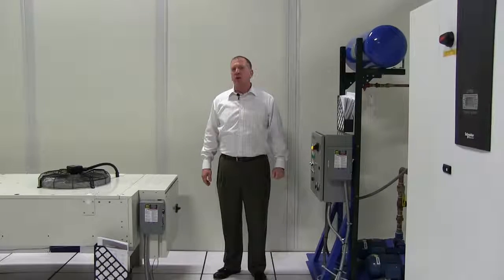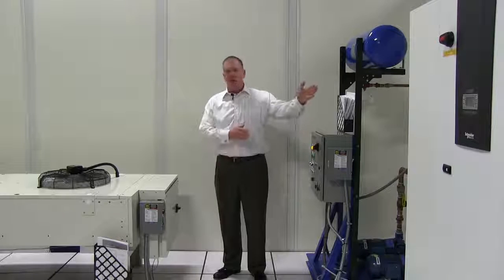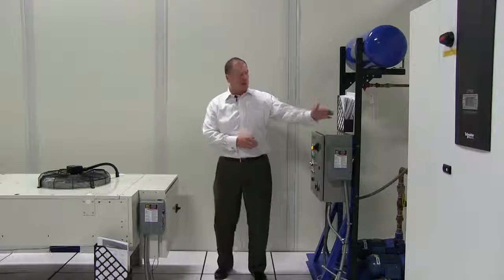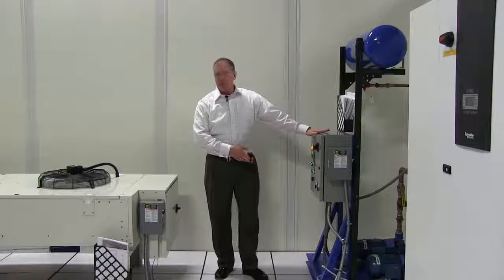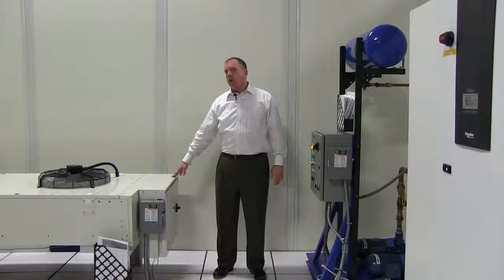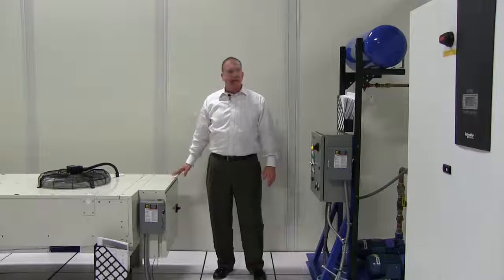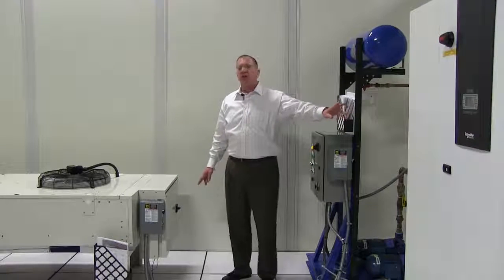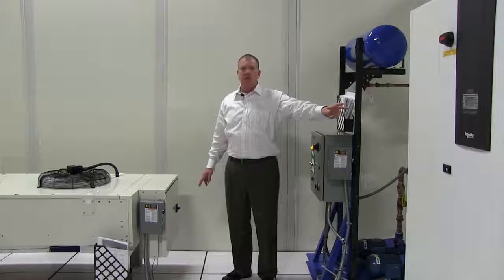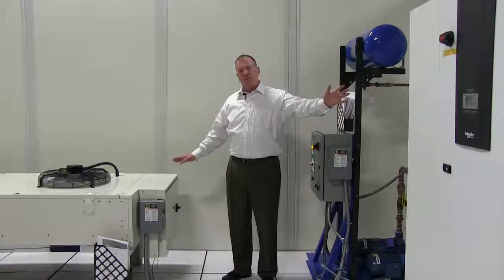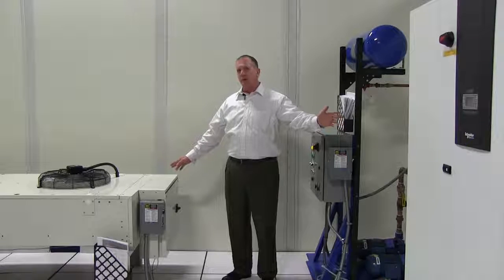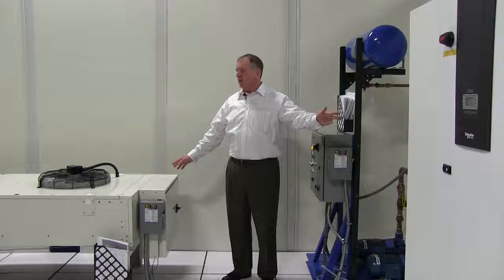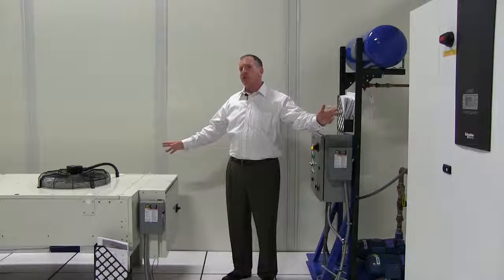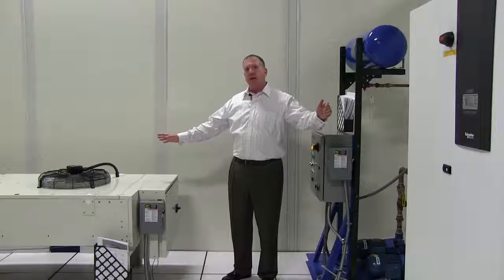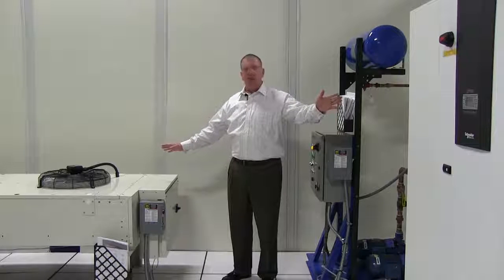Representing a typical glycol heat rejection loop, we have our indoor energy saving unit, a dual pump package, and an outdoor dry cooler for the heat rejection. On this system, where this is an energy saving unit and has the ability to do economization, we have 4 wires coming out to the dry cooler. 2 of them are the run signal.